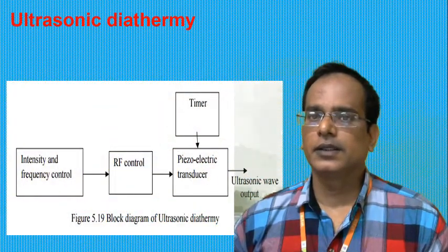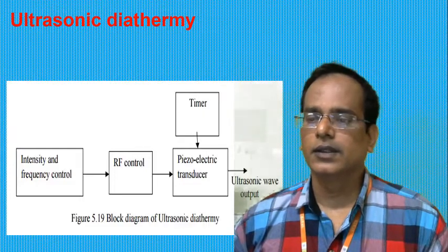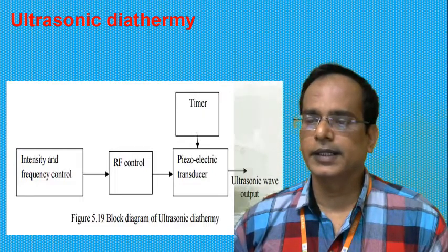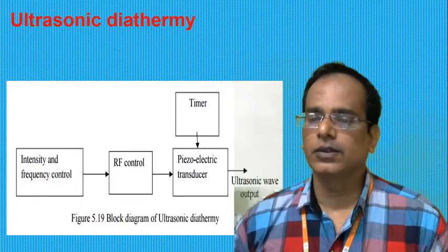So ultrasonic diathermy, that you are seeing here, has an intensity and frequency controller and an RF controller, which is given to the piezoelectric transducer, and another timer. So here the piezoelectric crystal is controlled with the RF controller, and also by the intensity and frequency level. Okay, so here the time duration also can be controlled by the timer.